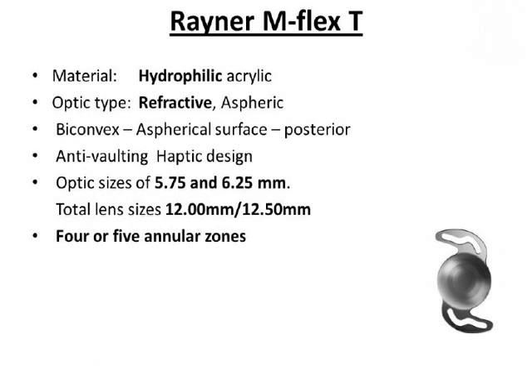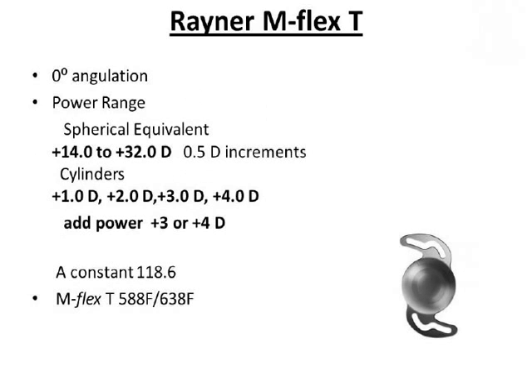The Rayner multifocal toric IOL is a hydrophilic refractive IOL having 4 or 5 annular zones. It is available in optic sizes of 5.75 and 6.25mm and an overall length of 12 to 12.5mm. It is available from +14 to +32 diopters in the spherical range and cylinders from +1 to +4 diopters. These IOLs have an add power of +3 or +4 diopters.